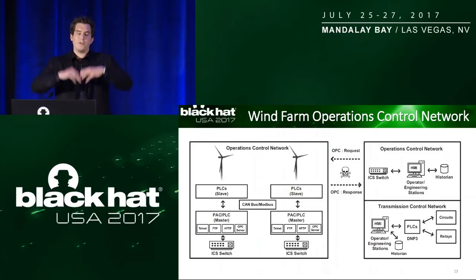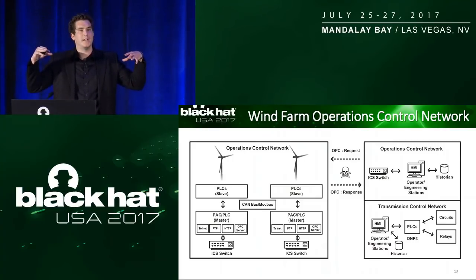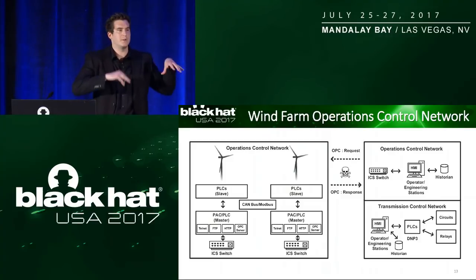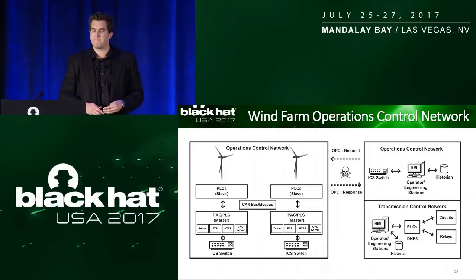They talk to other controllers at the top of the turbine and in the nacelle that are used to interface with the gears, the actuators, and the sensors. The protocols between these controllers usually are a common field bus protocol like CAN bus or MODbus.